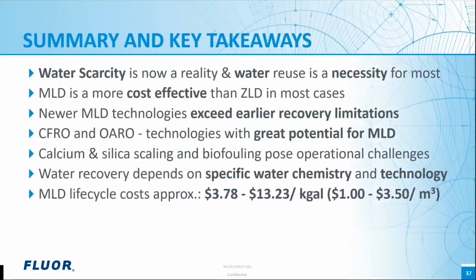So what are some of the key takeaways and summary of this presentation? First and foremost, water scarcity is now a reality, and sustainable water reuse is a necessity for most owners. MLD is a more cost-effective and less energy-intensive process than ZLD. Newer membrane technologies have exceeded previous threshold limits for scaling and pressure, which allow for higher water recovery. Counterflow RO and osmotically assisted RO are some good examples of new membrane technologies that have great potential for MLD applications. Calcium and silica scaling and biofouling pose operational challenges and need to have sufficient pretreatment in order to mitigate the impact on operation of the plant.